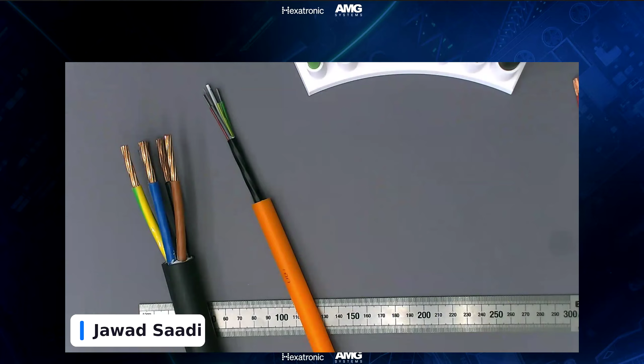Here at my desk I have a standard copper cable - this is 5 times 16 millimeters square, typical for distances in a CCTV network up to 400 meters. If you have any distance more than that, you need to go up to 32 millimeter square. Typically you run the AC cable to the access cabinet.